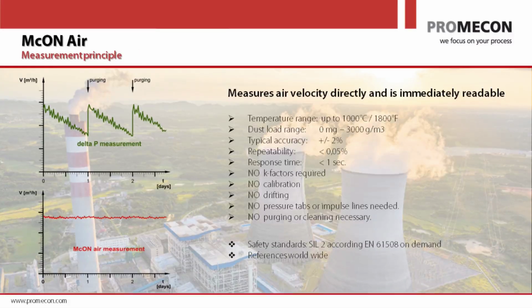Why is this so important? It is so important because this measurement will not drift over the lifetime of this system. So if you put the system in and 10 years later you check the calibration, it will be like on day one. And that's simply because we are only measuring time shift. We're not measuring anything else, right? The electrification that we measure, or the current, is only a timestamp that we use. We don't care about the current itself.